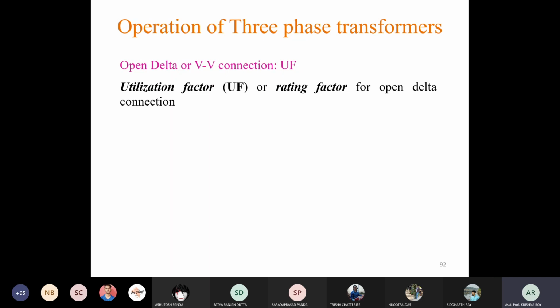So next is utilization factor or rating factor. What is the meaning of this? As we can see, the ratings or the capacity of the two existing healthy transformers is 2 V phase I phase, but we cannot use the full capacity of these two transformers while connected in open delta connection. So this ratio of actual used capacity and its installed capacity is called the utilization factor.